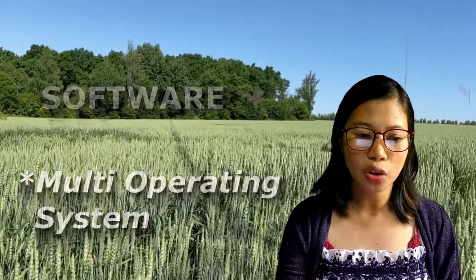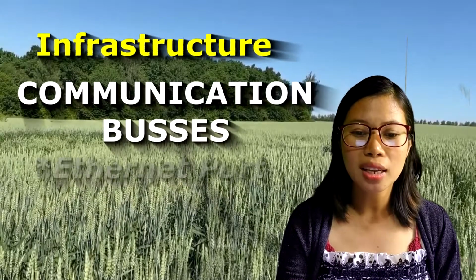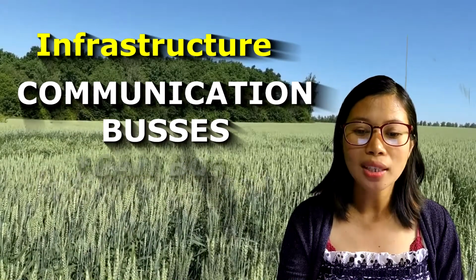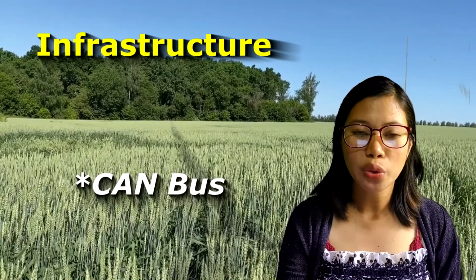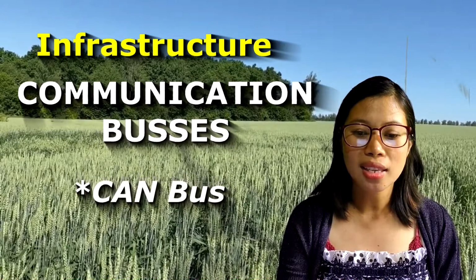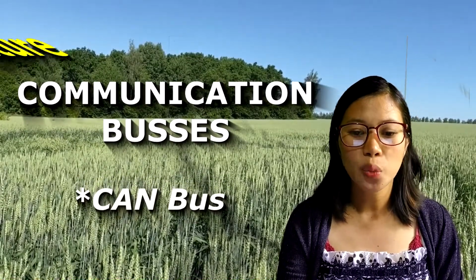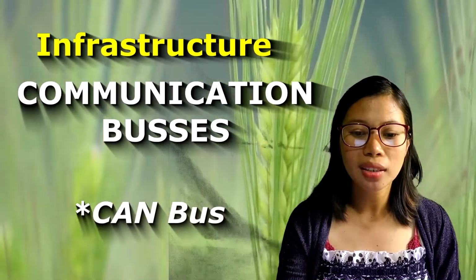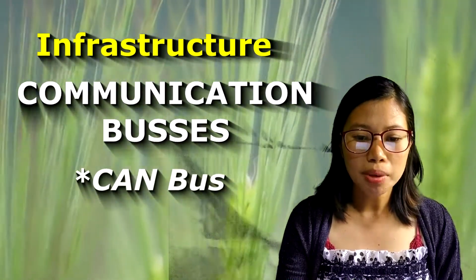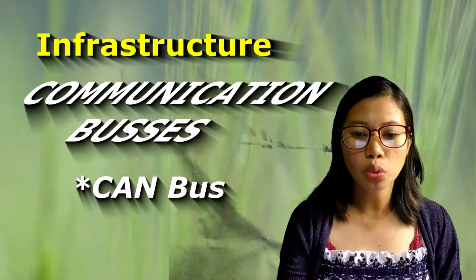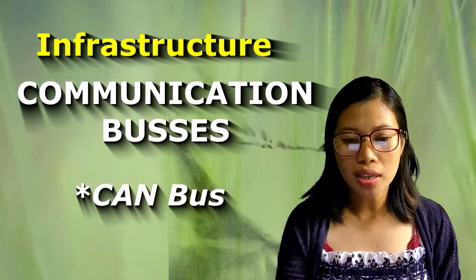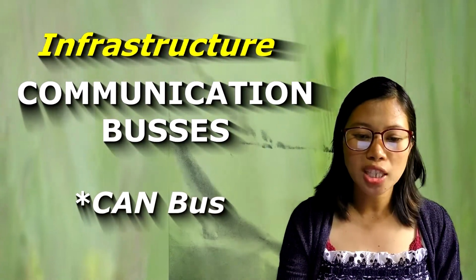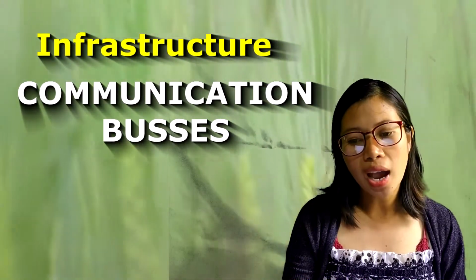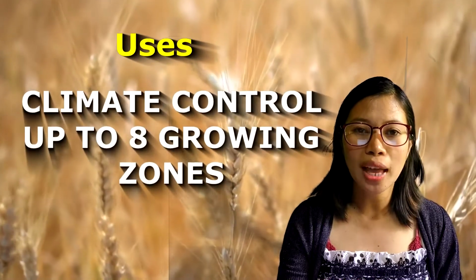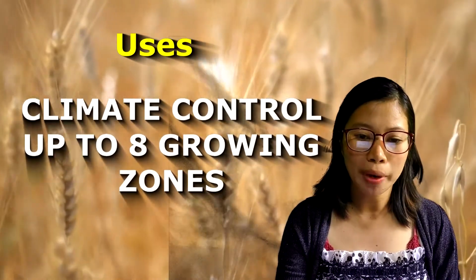For the software infrastructure, it has a multi-operating system, required for all systems that have multiple compartments for climate plus dosing and fertigation. For communication buses, there is an Ethernet port, and one CAN bus connects to the station. And then a second CAN bus connects its controller with its local peripherals such as aspirated environment sensor boxes, temperature, RH, solar, CO2, pressure, dosing sensors, EC, pH, and moisture, output expansion modules with overrides, analog I/O modules, and etc.